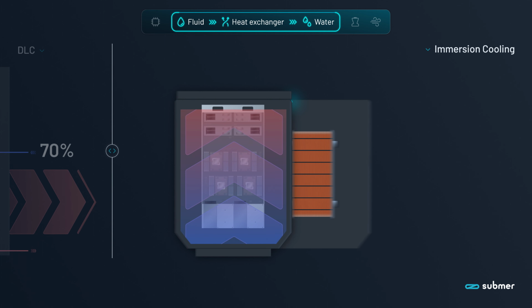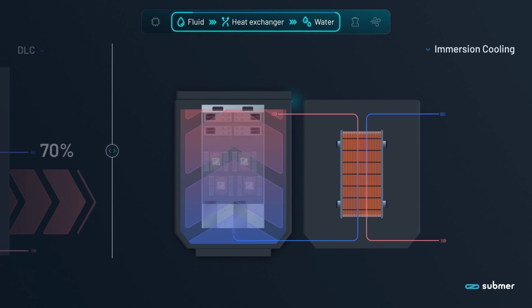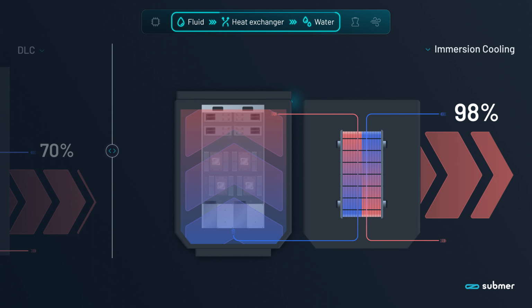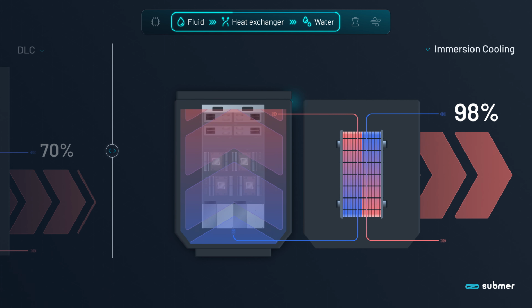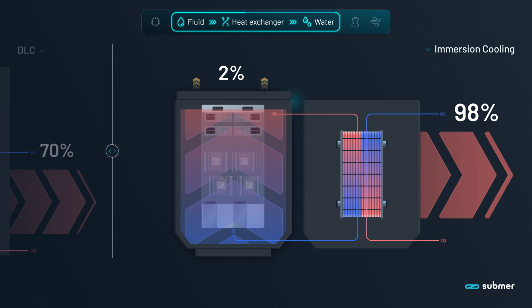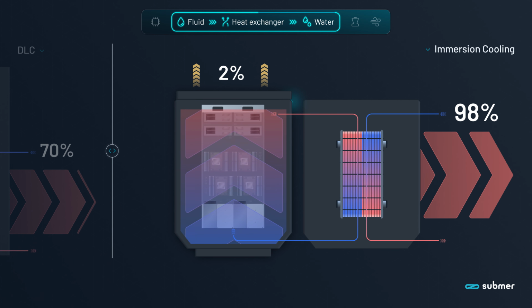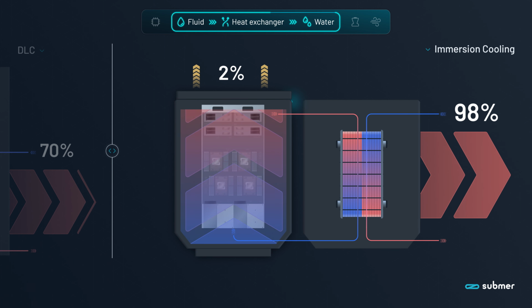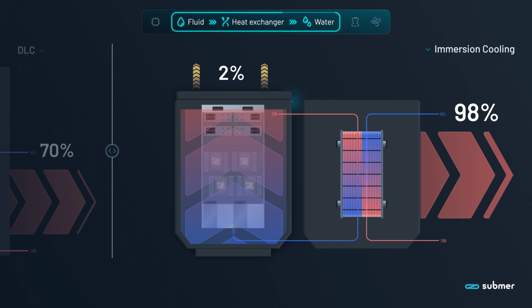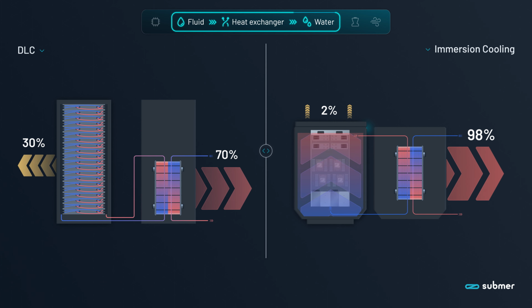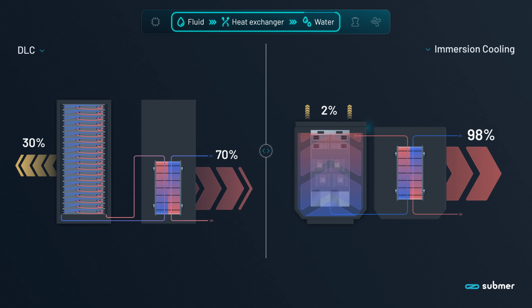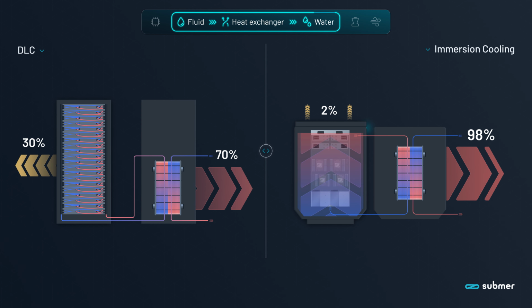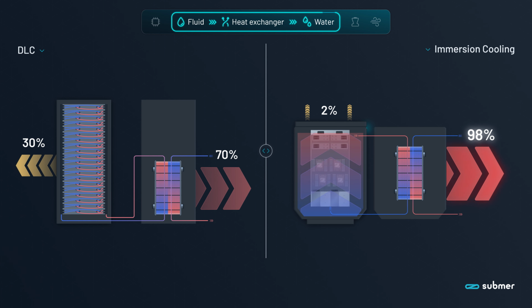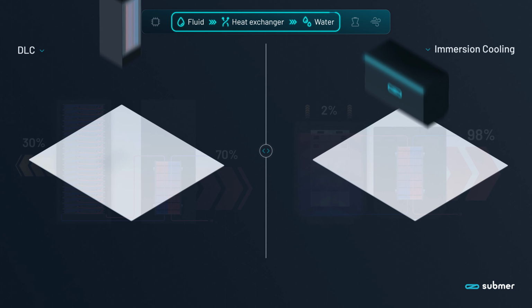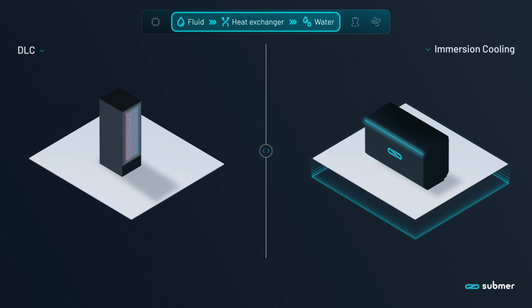In immersion cooling, the hot immersion fluid is transported directly to the heat exchanger in the CDU, where it transfers 98% of the heat to the secondary fluid. The remaining 2%, originating from the ports and piping, is effectively managed by simple air handling units. At the second heat transfer stage, the simplicity of immersion is clearly visible. Moreover, it offers the advantage of concentrating the majority of the heat into one body of fluid. Simplicity brings reliability.